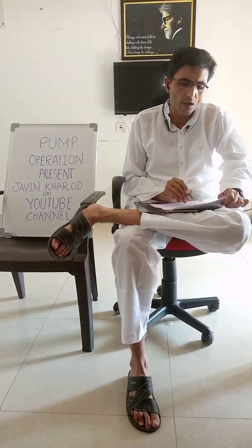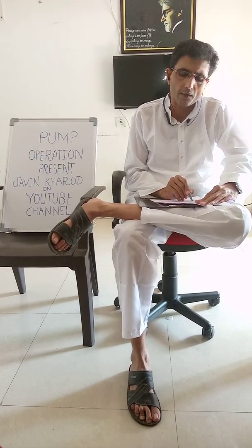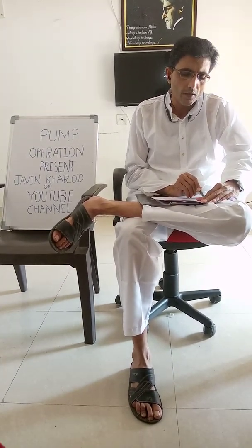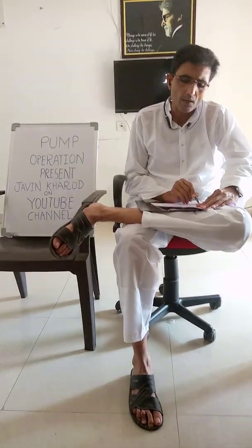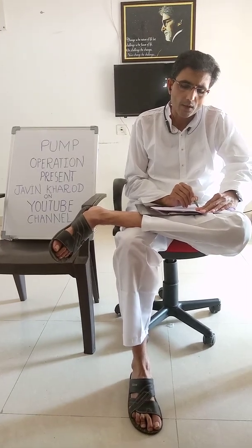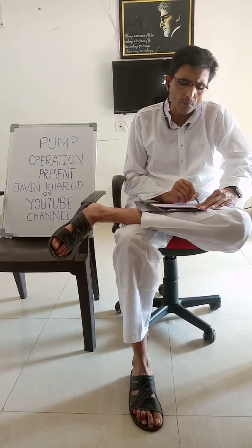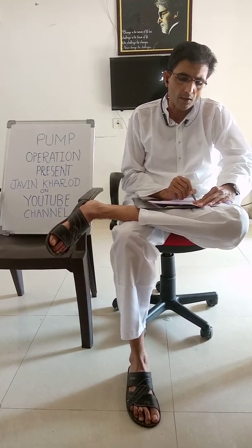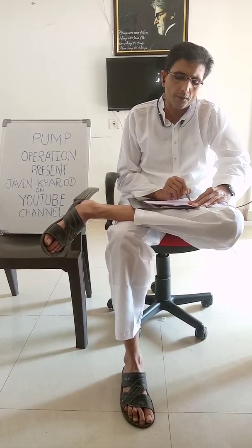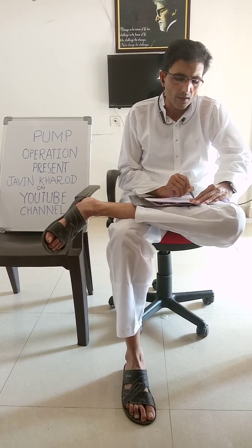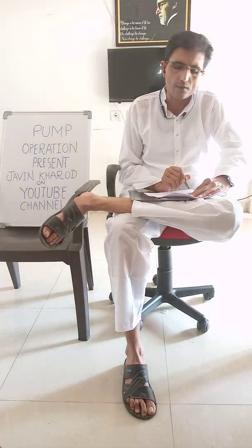Now, specification. Pumps are commonly rated by horsepower, flow rate, outlet pressure in feet of head, and inlet suction in feet of head. The head can be simplified as the number of feet or meters the pump can raise or lower a column of water at atmospheric pressure. From an initial design point of view, engineers often use a quantity termed the specific speed to identify the most suitable pump type for a particular combination of flow rate and head.